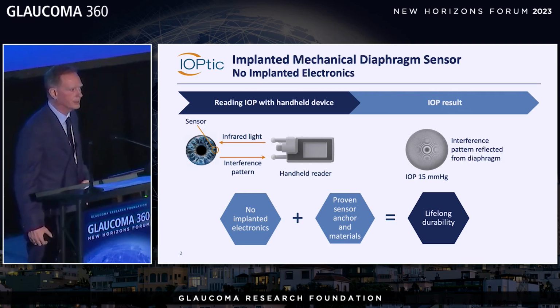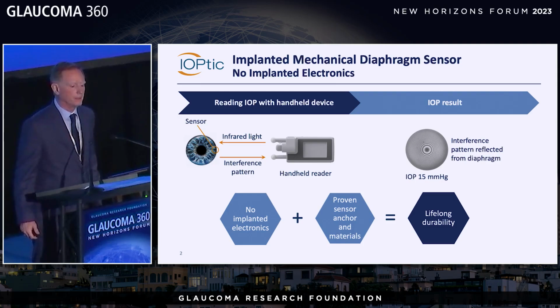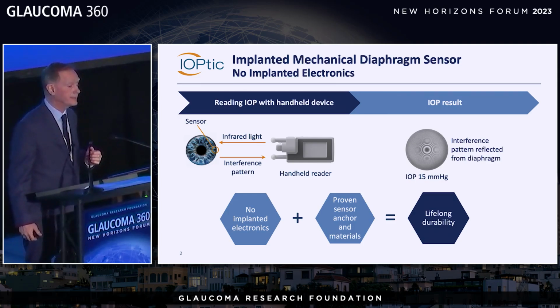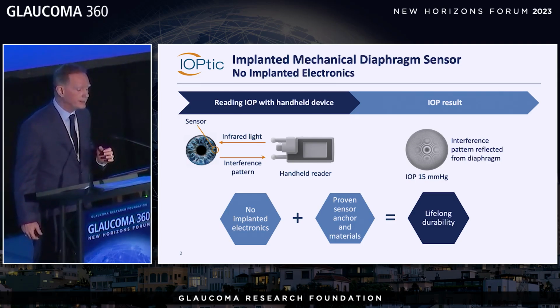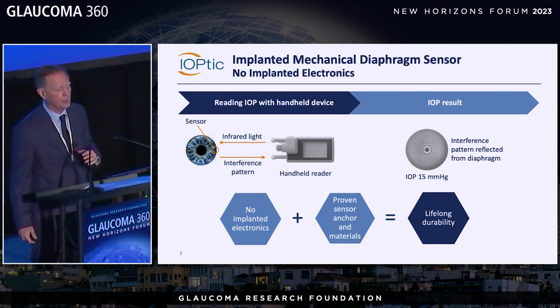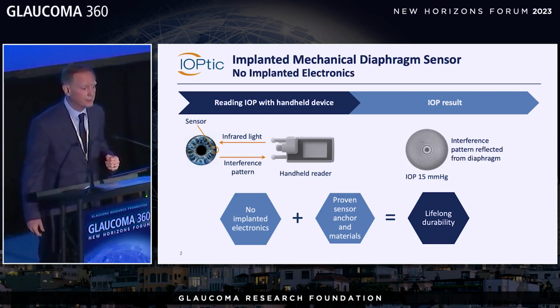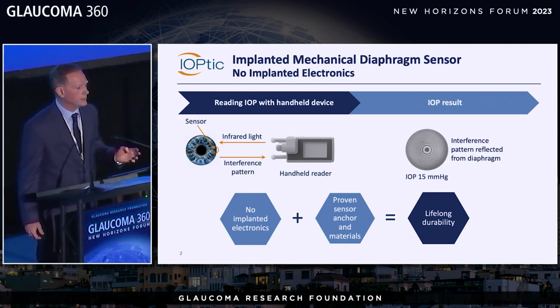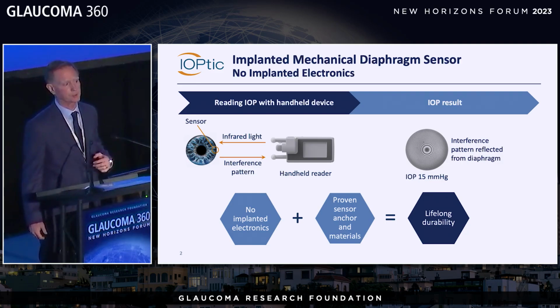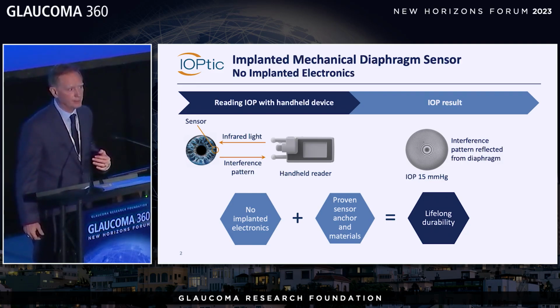The device consists of a very small pressure sensor that's permanently implanted and a handheld reader. The pressure sensor is a mechanical diaphragm, which is a very thin membrane that changes shape as the pressure changes. The handheld reader has a light source that illuminates the diaphragm and a camera that takes a picture of an interference pattern that reflects back from the diaphragm, which gives us the pressure very accurately to within 1 millimeter of mercury. You see the sensor is attached to the iris, and there are no implanted electronics. That's what sets our device apart from other implanted pressure sensors.